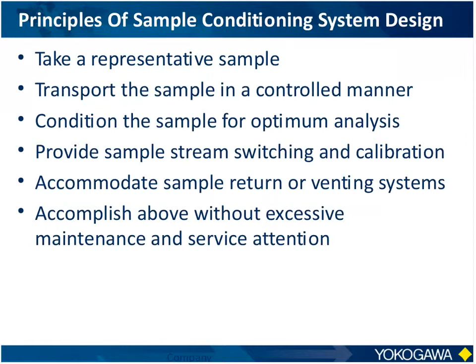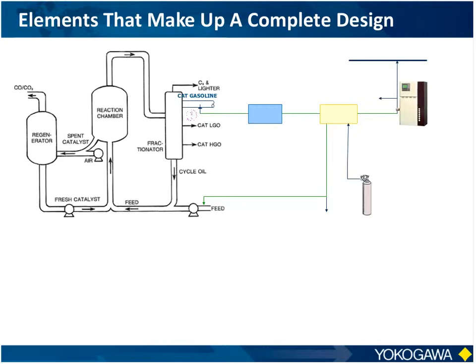So here's an example of an application where you can see the different sample system elements involved. In a refinery, I have what they call a cat cracker, and I have an analyzer here, and I want to take a sample of one of the streams. So I've got my sample takeoff of the gasoline line. I then have a primary sample system where I might do some pressure and temperature control and maybe a little bit of filtration very early. I then need to transport the sample, again, in a controlled manner so that it doesn't condense or whatever. I need to do the final cleaning: the temperature, the pressure and the filtration.